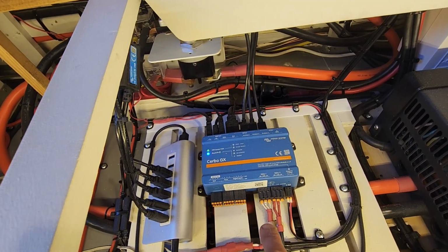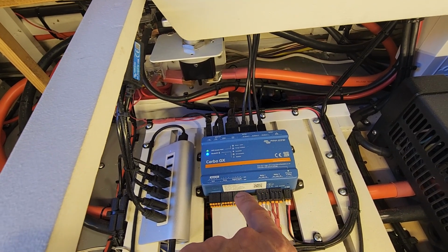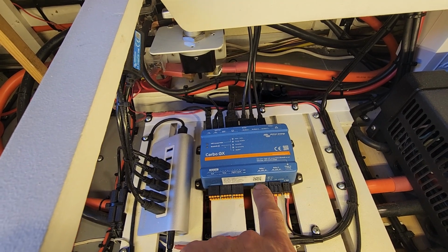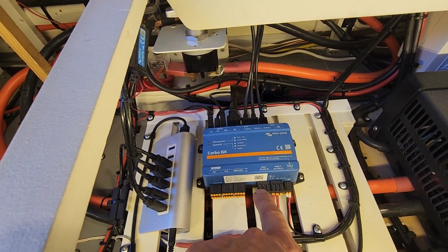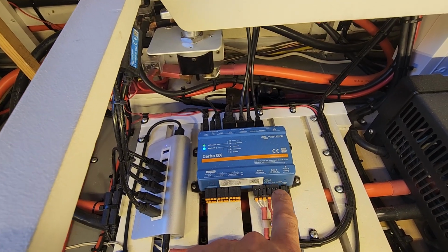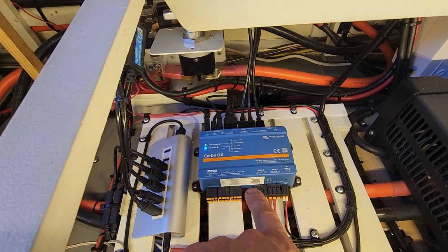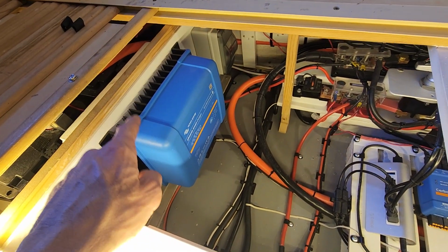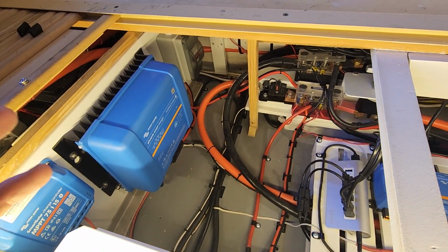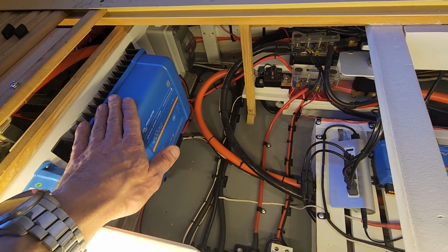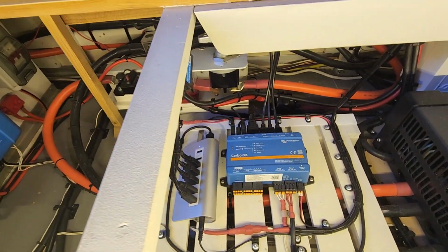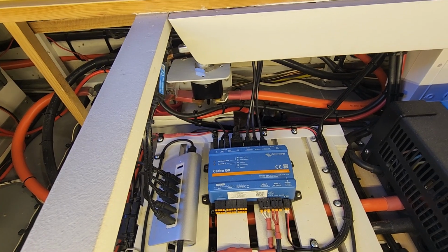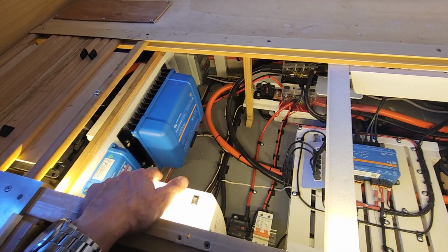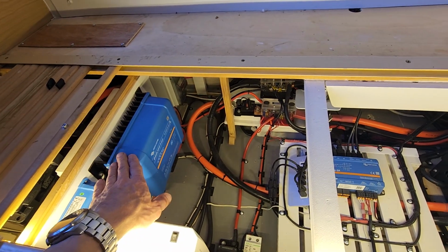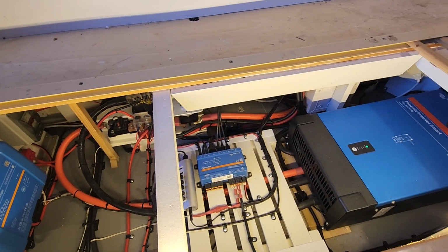So when the battery system gets down to 70%, the Cerbo GX, through its start-stop relay, cuts off the transfer switch, and then the AC automatically fires up, and at the same time my two IP43 chargers start up. Each one of the IP43 chargers is hooked up together through their relay. So then when it gets back up to 100%, the transfer switch then starts back up and everything's running off the batteries again, and the battery chargers stop because the mains stop. So it works out really well.